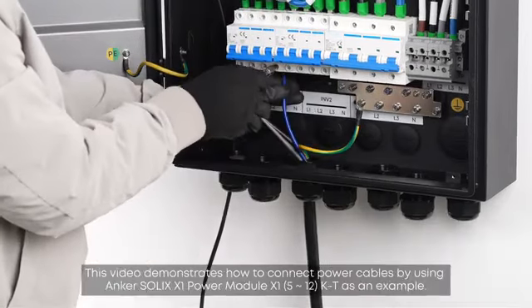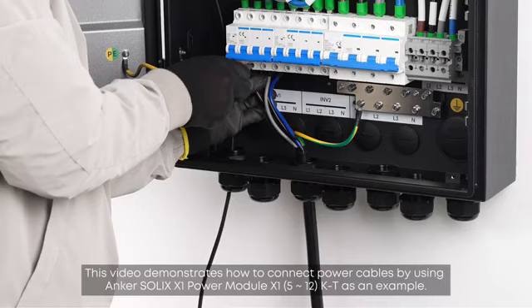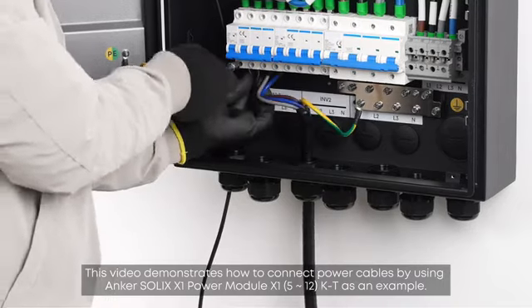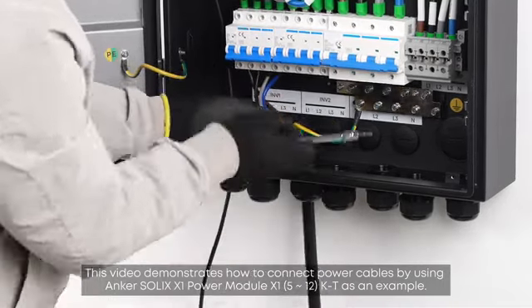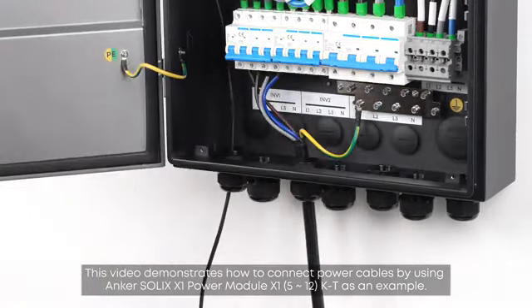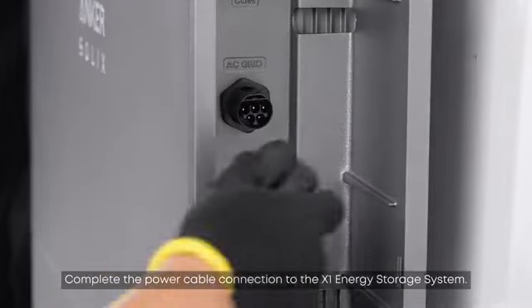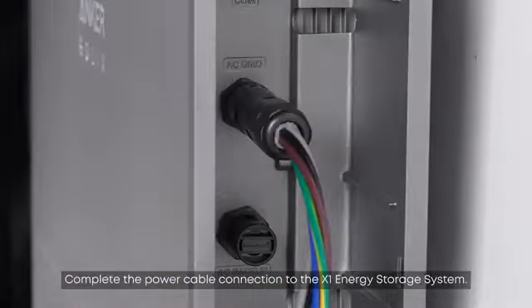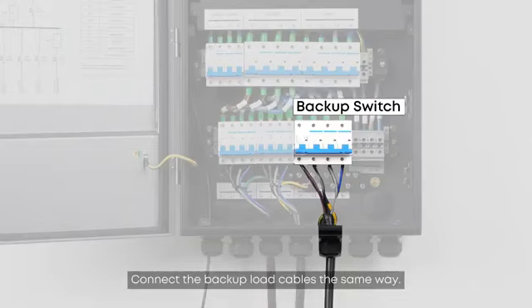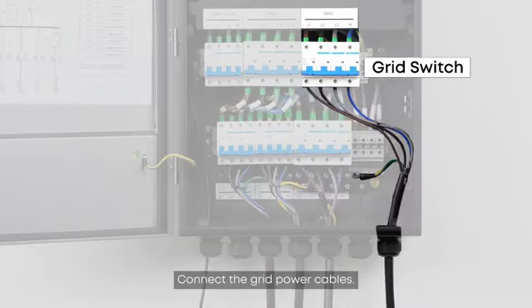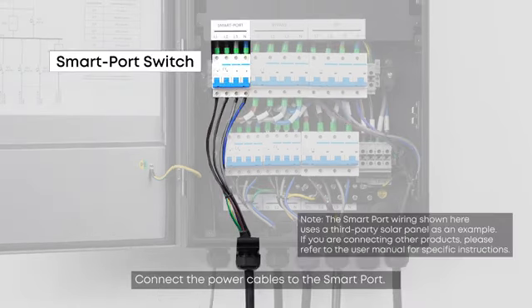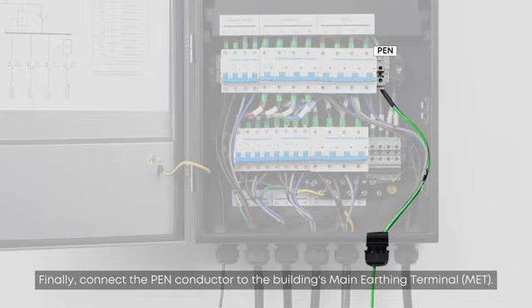This video demonstrates how to connect power cables by using Anker Solix X1 power module X1 5-12 KT as an example. Complete the power cable connection to the X1 energy storage system. Connect the backup load cables the same way. Connect the grid power cables. Connect the power cables to the smart port. Finally, connect the PEN conductor to the building's main earthing terminal, MET.